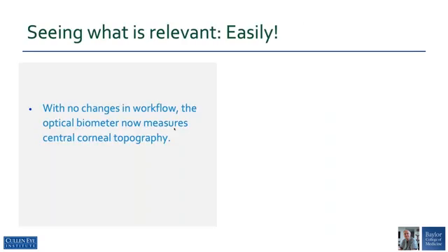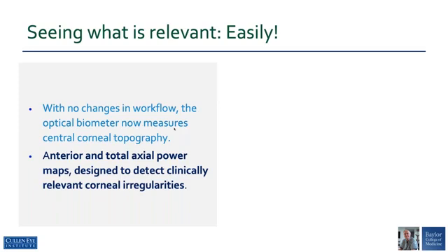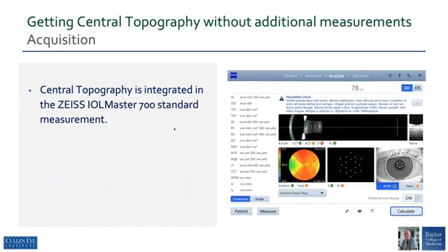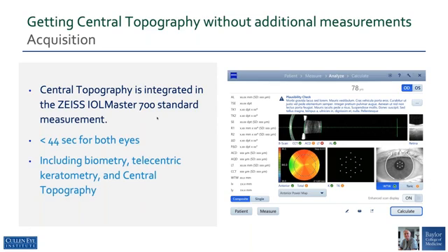This has been implemented in the IOLMaster in a very unique way so that with no changes in your workflow, the device now measures central corneal topography, in which anterior and total axial power maps are displayed that will provide the clinician with a very quick but fairly comprehensive view of corneal irregularities. The display is now integrated with the B-scan, the white-to-white, the LEDs, and total central topography. The measurement takes less than 44 seconds for both eyes, and includes the biometry, telecentric keratometry, and central topography.